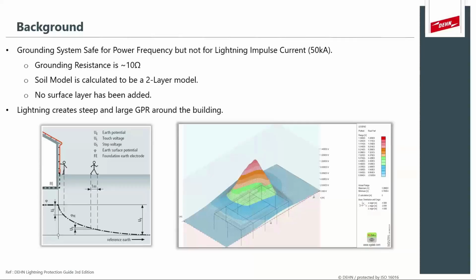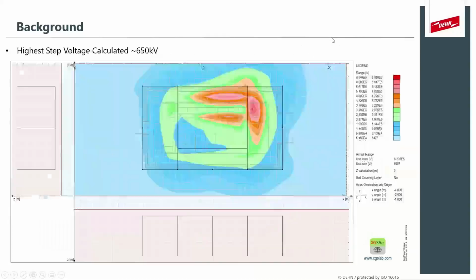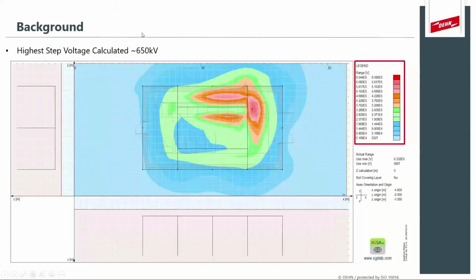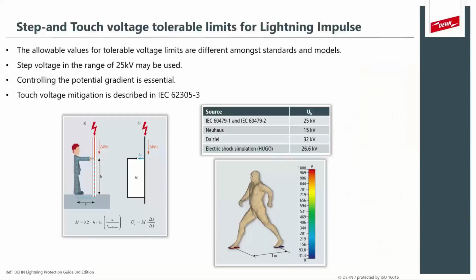So if we just want to start the investigation to see what we are working with, we inject the 50 kiloamps into the same earthing grid at high frequency. And you can immediately see the step voltage is calculated to be around 650 kilovolts for the 50 kA first negative stroke. In this case, it's also estimated with a 250 kilohertz sinusoid. Now, the 650 kilovolts is far above what is considered safe for lightning step limits, or allowable limits. There are a lot of different theories and calculations and models around what's seen as the allowable step touch voltage limit when we speak about lightning.